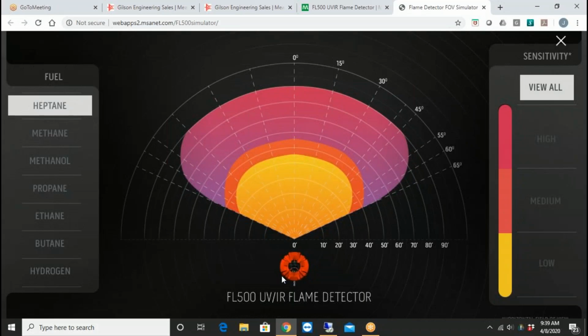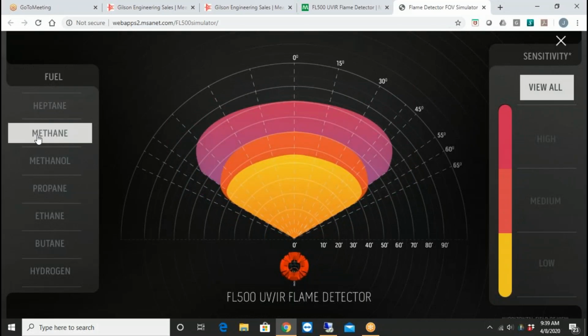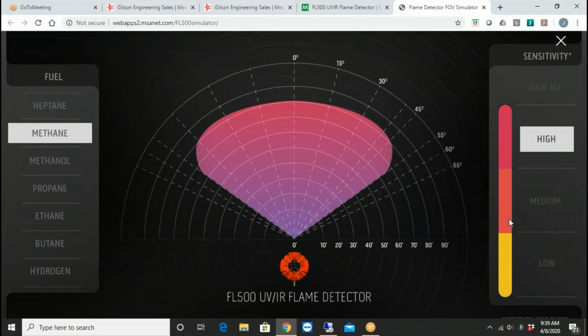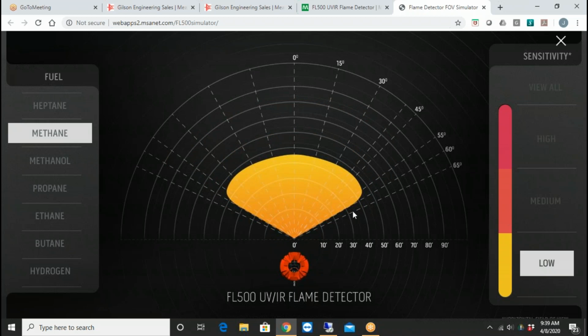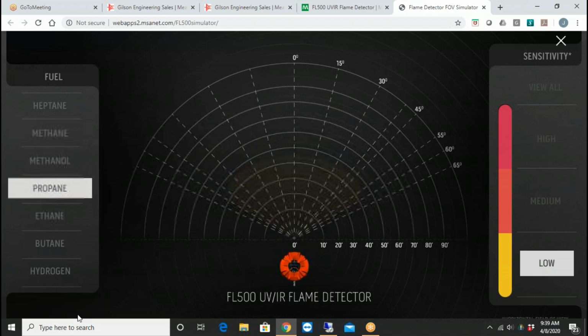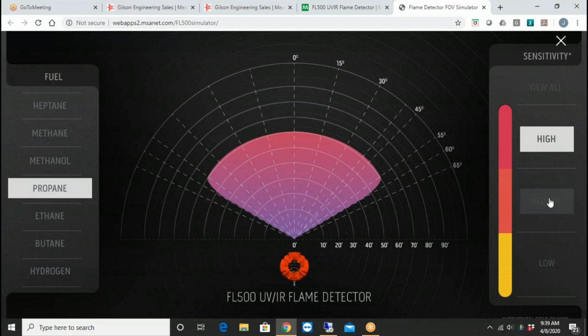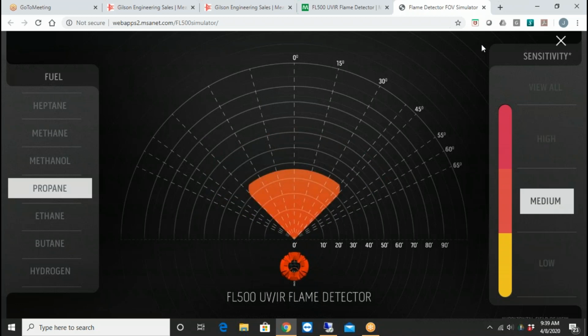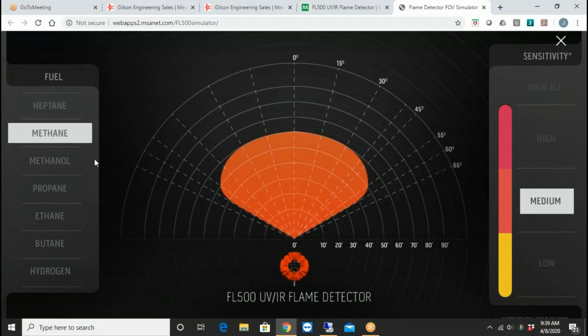This is a good way of visualizing the coverage beam angle for different fires. You can click on a fuel over here and then select a sensitivity curve that you want to look at, and it will give you angles and distances and so on. So it's an easy way, if you've got some propane bullets that you're trying to protect, to click on that and instantly get a graphic as to what kind of coverage that detector is going to provide, and then switch it over to methane and see how that correlates with the same unit. So that's one here on the MSA website.